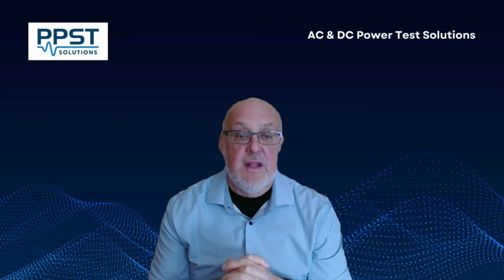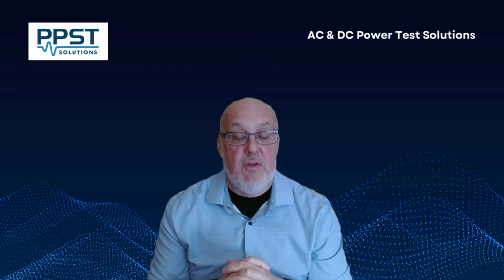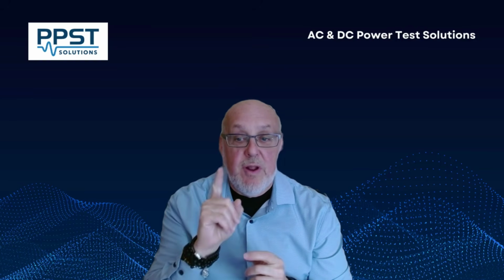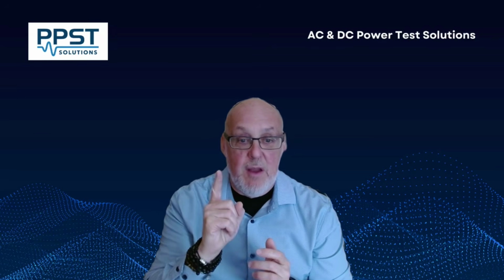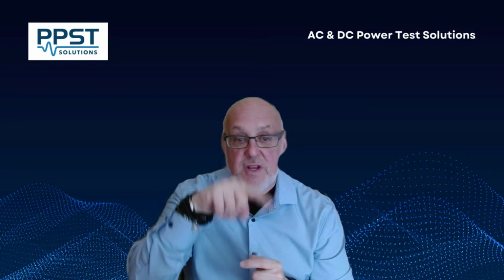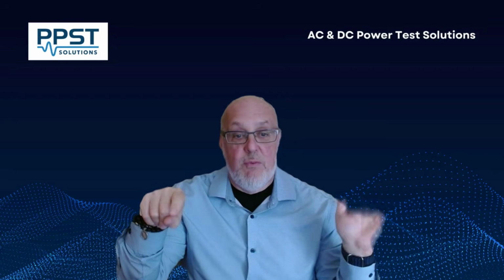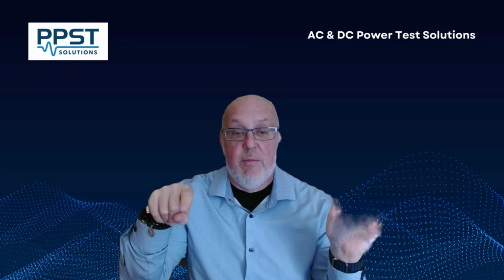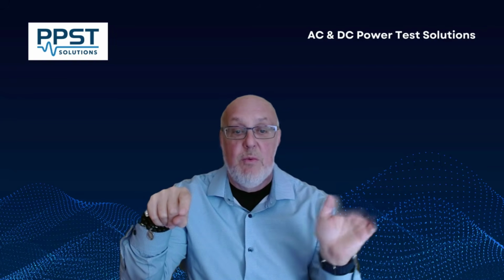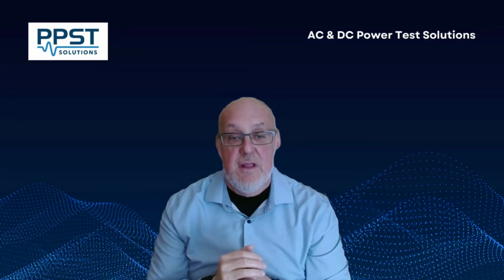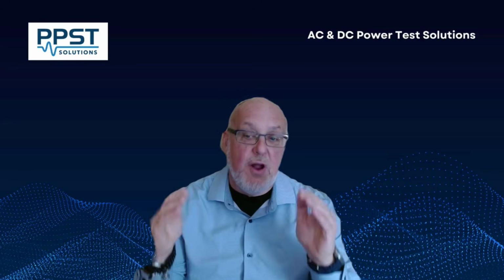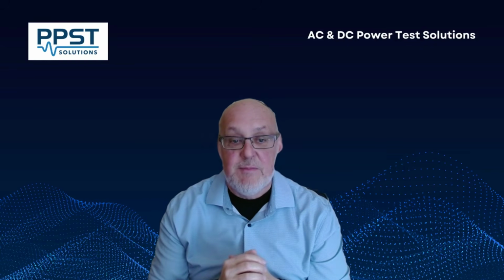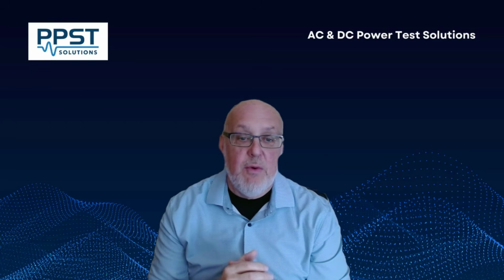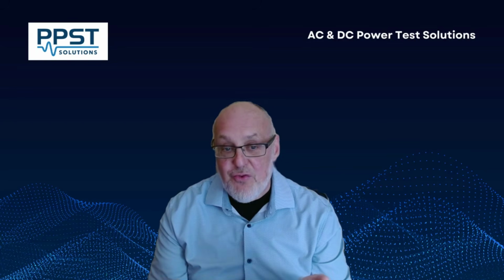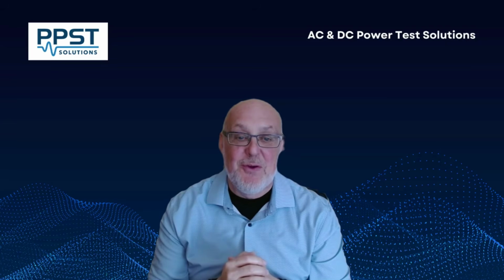So that's typically less than 10% of energy losses that we're having. So we're burning 1 megawatt, and out of that 1 megawatt, we're only utilizing 100 kilowatts of energy. The rest of the energy is just circulating. What that means is we're not drawing 1 megawatt from the utility company anymore. We're just drawing 100 kilowatts. And so our energy consumption drops by 90%. And if you're looking at a 24-hour burn-in, especially in California, as you can imagine, those rates can be very high.